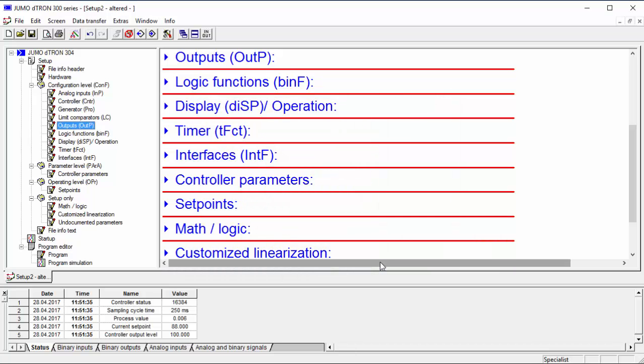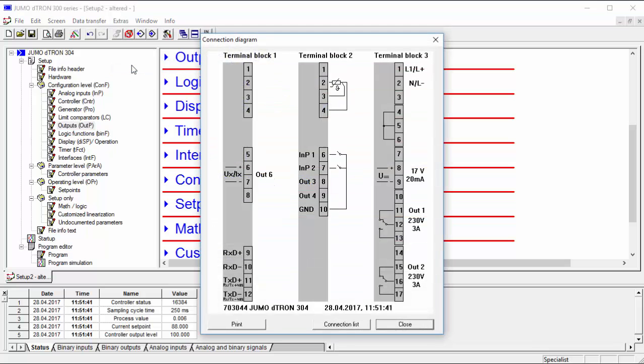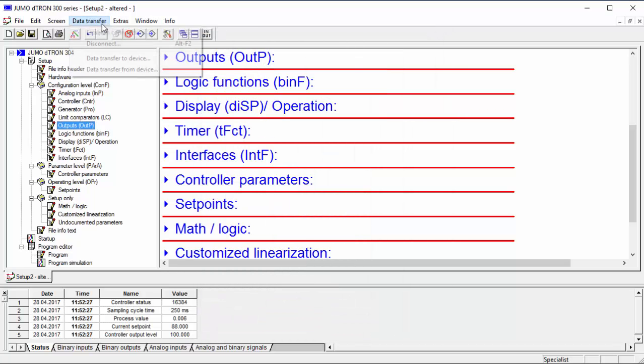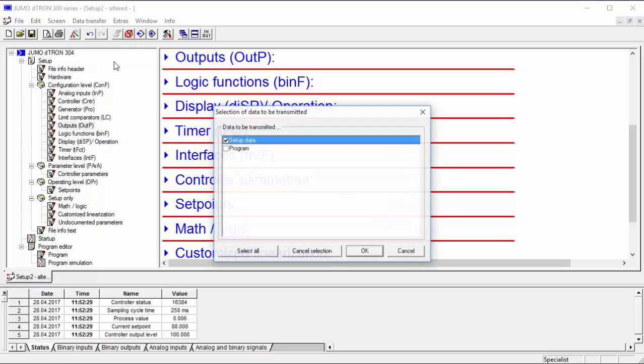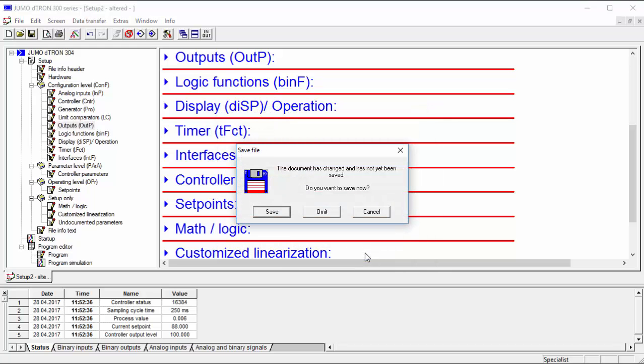For wiring of the components, the function connection diagram is helpful. The RTD temperature probe is connected to terminal 2 to 4 of terminal block 2. The power controller is connected to terminal 6 and 7 of terminal block 1. If required, the configuration file can be saved.